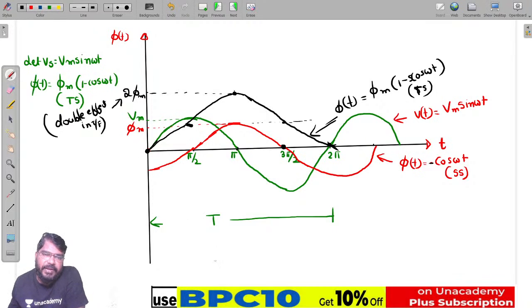So how do we define the doubling effect here? The flux produced in the transformer gets doubled. It doubles to 2 times the maximum value of the flux under steady state condition. Under transient condition, this is known as the doubling effect.